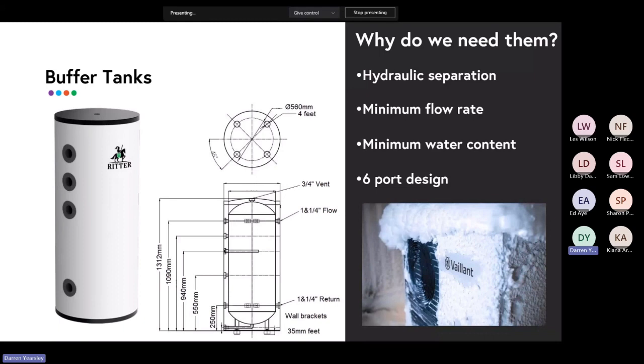So hydraulically, the way we set them up is we have an array of appliances. If we're doing hot water production, for instance, we always have a minimum of 2. So we've always got some redundancy built in. And hydraulically, it connects onto a buffer tank, which hydraulically separates the appliances from the load. I'll show you a drawing in a second. And what that allows you to do is to run the cascade in a very optimal way. So if only one heat pump needs to run, then there's no water going through heat pumps 2, 3, 4.